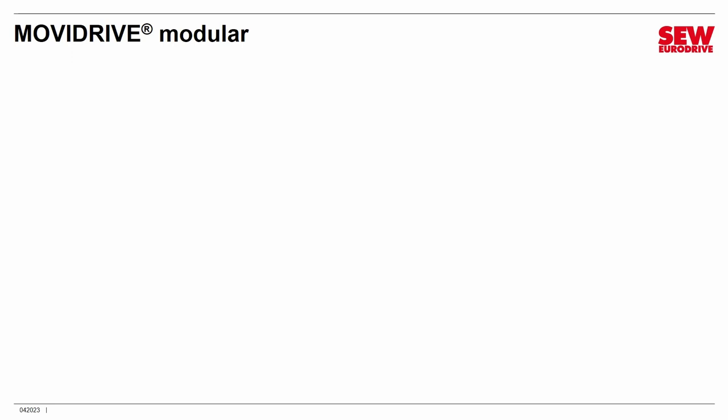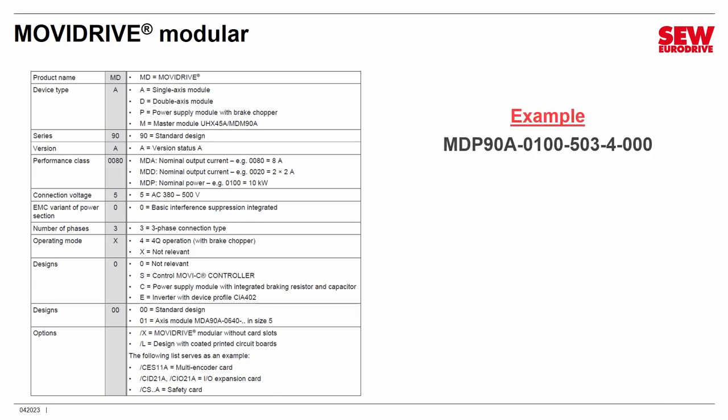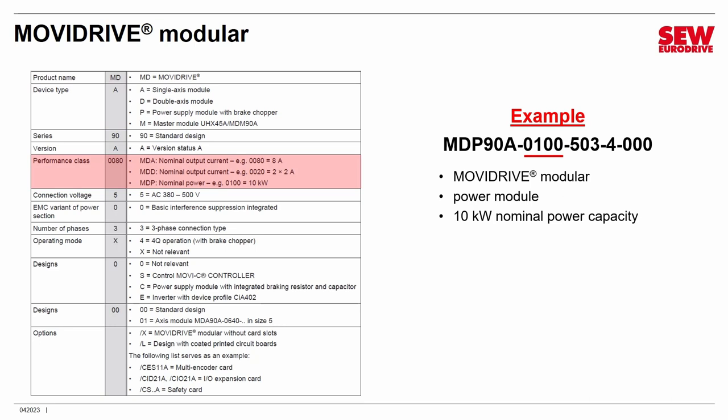One more nomenclature exercise: MDP 90A-01-00-503-4-000. MD means MoviDrive and P means power supply module — this is the nomenclature for a MoviDrive Modular's power module, which all MoviDrive Modulars must have as part of them. These are rated in kilowatts — pretty much the only MOVI-C control cabinet product that gets a kilowatt rather than an ampere rating. Using the same decimal point rule, the rating here is 10.0 kilowatts, so this is a 10 kW power supply.